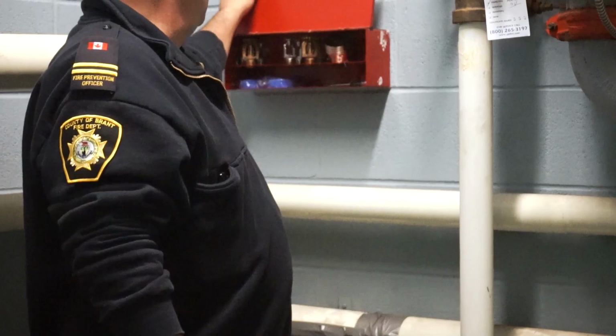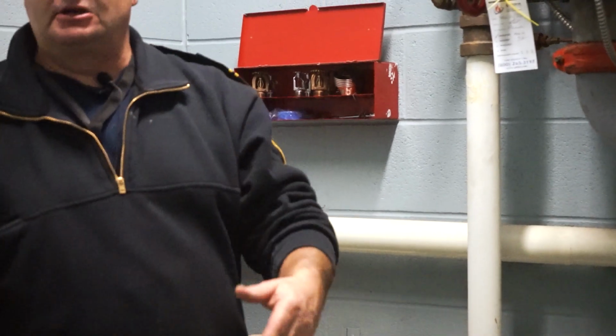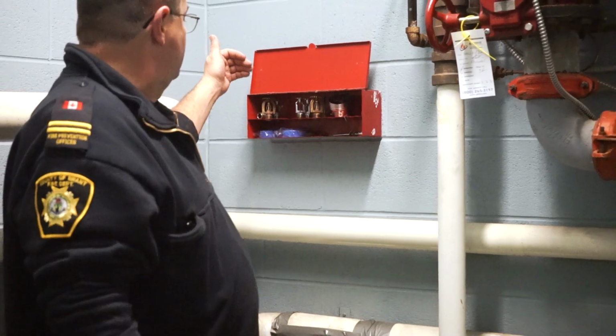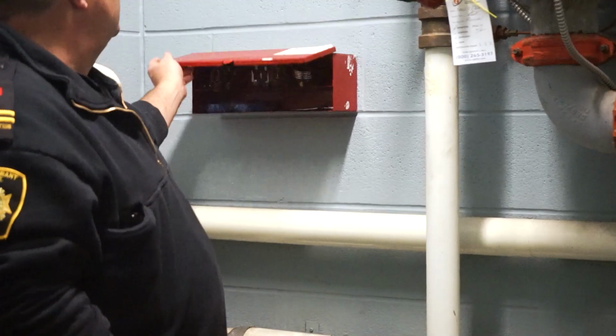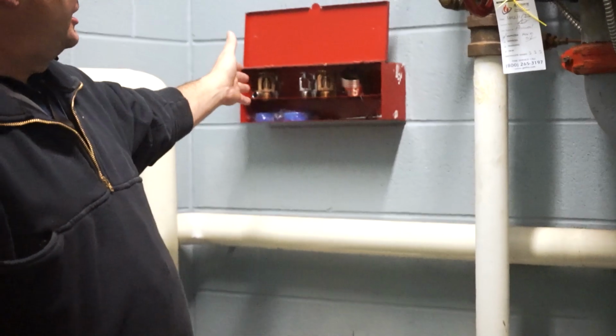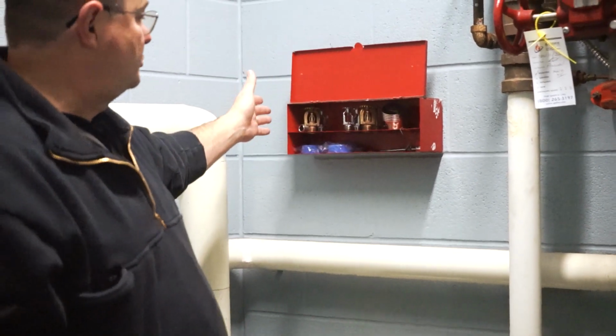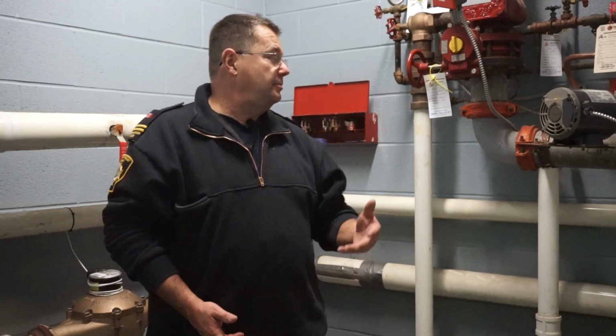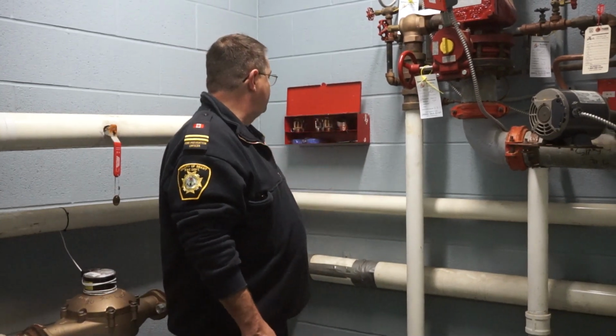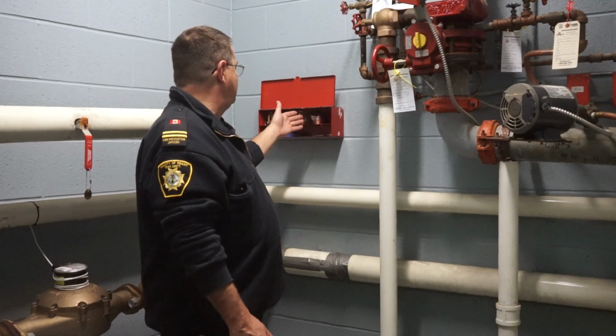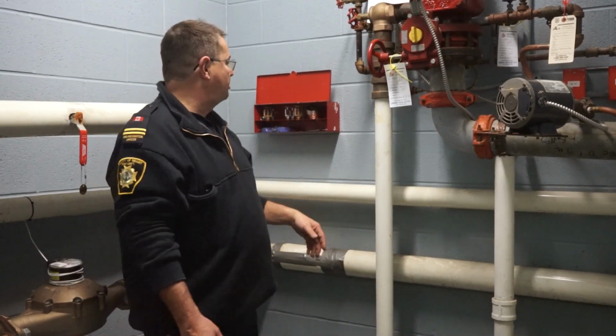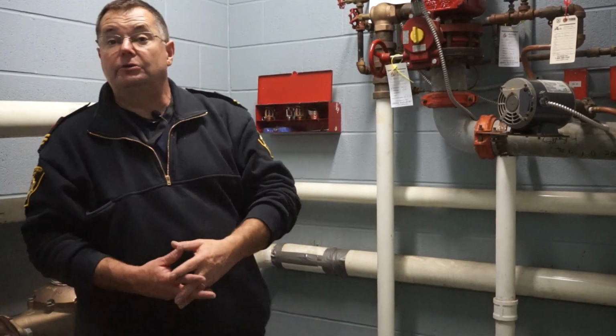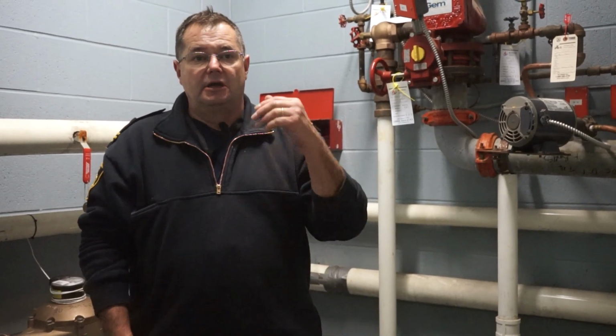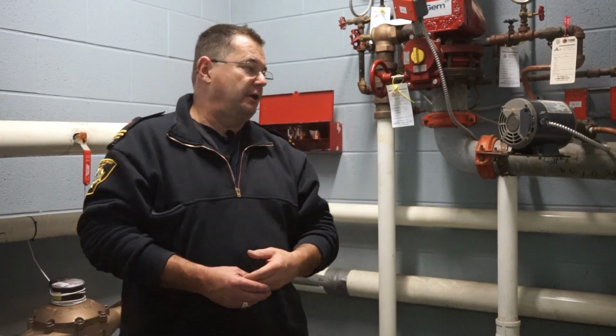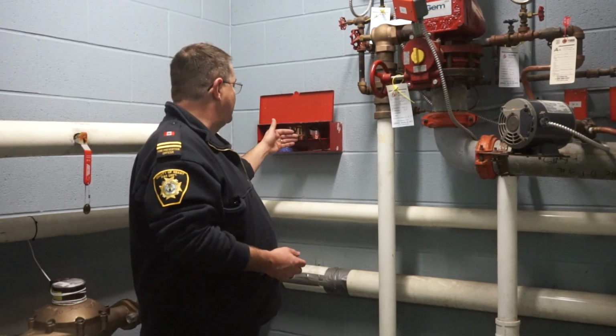So we make sure that there is a minimum standard of spare sprinkler heads on site. Different versions of this come in sizes for 6, sizes for 12, 301 heads in this building. They're only required to have 6 spare sprinkler heads in this, and by the count on this box, we have a couple extra, and there's no problem with that. With this though, you need to maintain an assortment of sprinkler heads for all the different uses of sprinkler heads within your building. So we can have upright, sidewall, pendant.